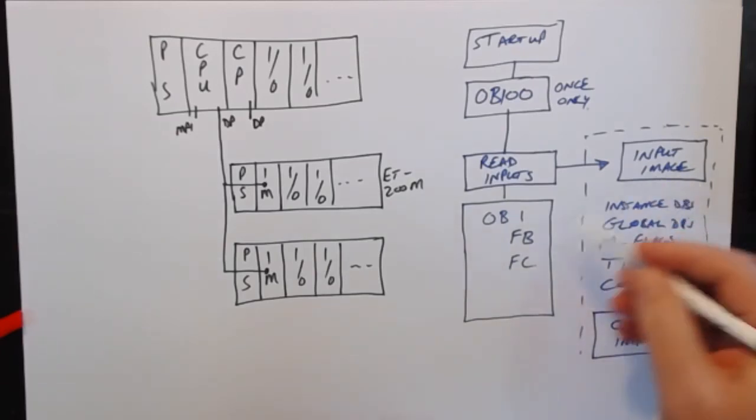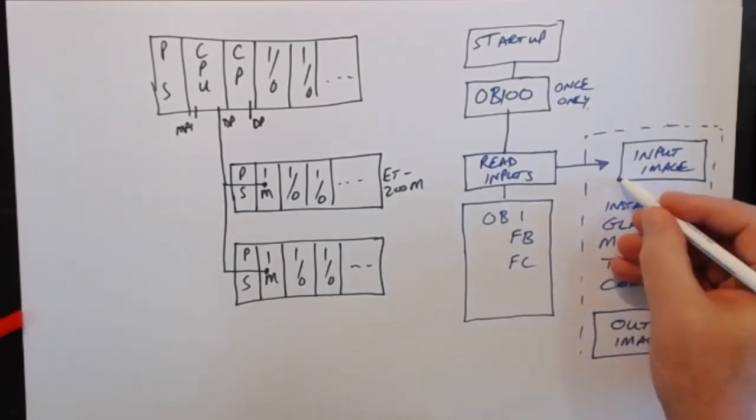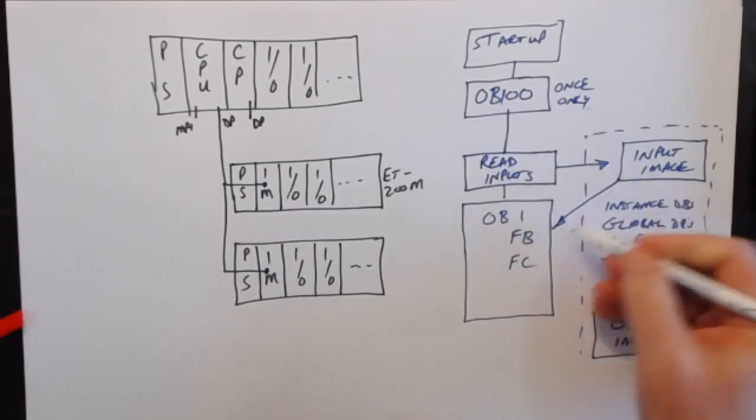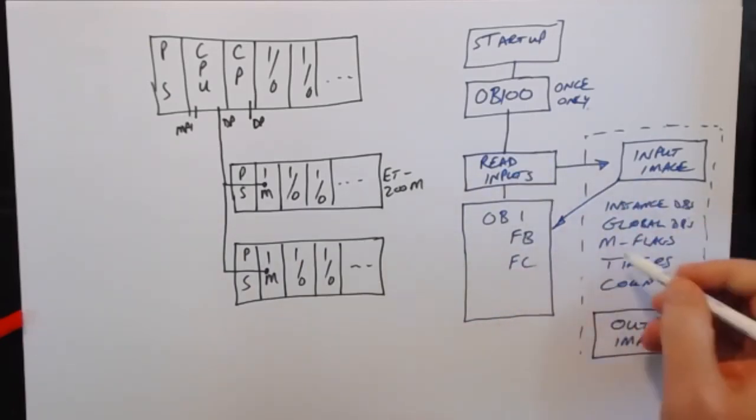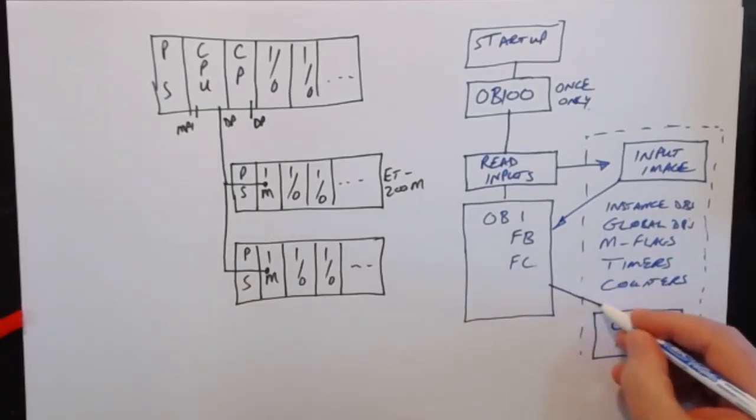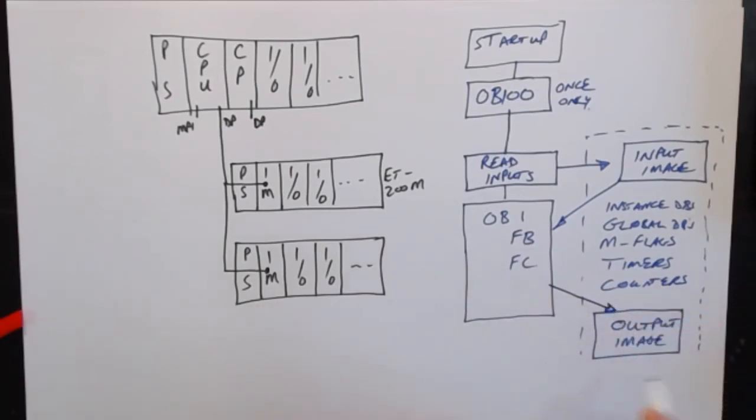When your program is running, it's taking information from the inputs. It doesn't read directly from the hardware, it reads from the input image. It operates on all that to create your program state, and then from that it writes and modifies the output image.